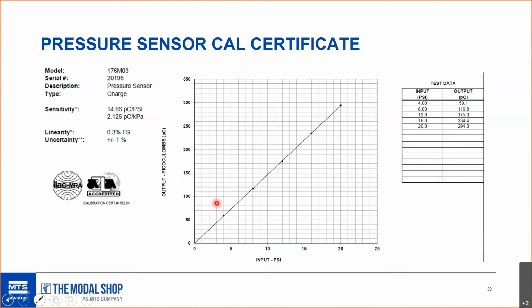What do you think? I mean, combustion dynamics is kind of down there in the 1 to 5. If you were doing that type of application, would you run it to the full scale, which is usually 20, or would you stop at 5, or is it completely up to the end user? It's up to the end user. And no standard or anything. Like I talked about, a good standard is repeating what the manufacturer does. Yeah. And this is the manufacturer technique at PCB.